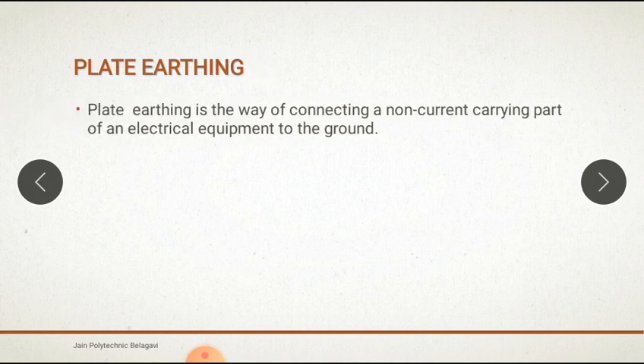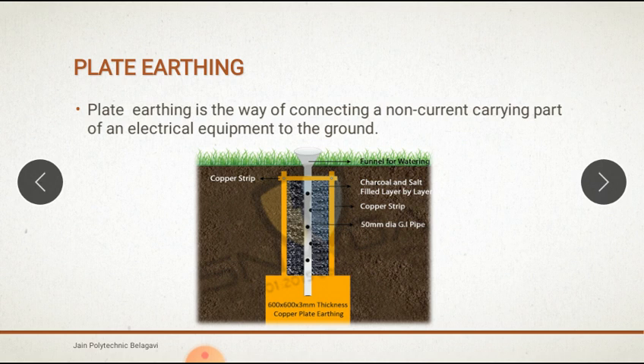Plate earthing is the way of connecting the non-current-carrying part of an electrical equipment to the ground. This is the diagram of plate earthing - showing the plate, the panel of wiring, and the copper strip, which is filled with alternate layers of salt, sand and charcoal: one layer of salt, one layer of charcoal, and one layer of sand.